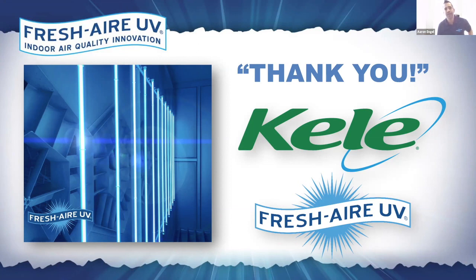Taking that a little bit further, a stagnant drain pan is a huge issue. And this is one point I just can't stress enough: it's all great to talk about SARS-CoV-2 and how important it is to inactivate viruses in the air, but we've been doing ourselves a disservice all these years by not addressing the air handling unit. With a drain pan, stagnant water, Legionella could certainly be an issue inside the drain pan as well. As I mentioned multiple times during the presentation, addressing the evaporative coil and the air handling unit is definitely a great strategy. So I don't think we really want to do cooling towers right now, but we could solve part of the problem with normal air handling maintenance and disinfection.